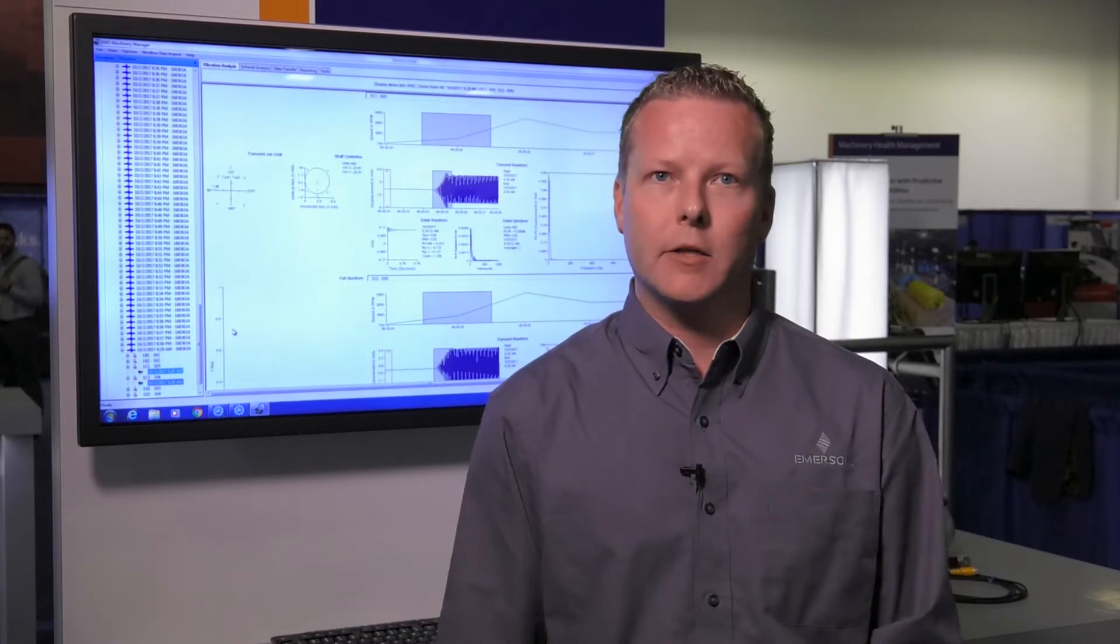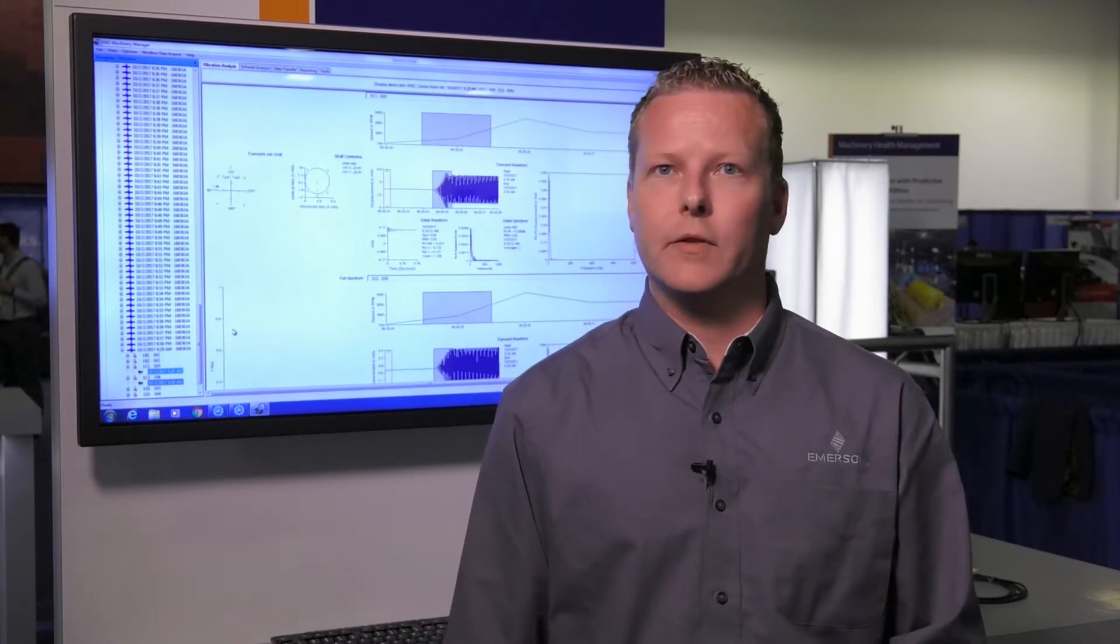Therefore, just the Modbus data import functionality of Machinery Manager and the software itself need to exist and be enabled to work with this data. For sure, this includes the first mentioned predictive diagnostics and a 400 lines of resolution waveform.